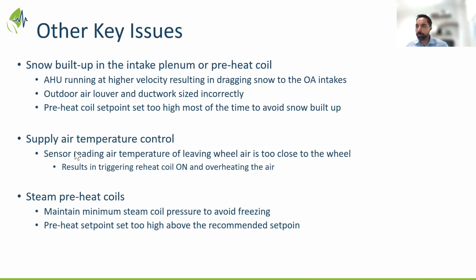The next one is supply air temperature control, which again goes back to where the sensors are located, especially the sensors located close to the wheel's leaving temperature, because these are huge units. The wheels are big, and it takes time for the air to mix. If you have a sensor downstream of the wheel, it could read different temperatures anywhere from 0 to 10 degrees C. That sensor is connected to a PID loop that brings on the heating coil to reach the supply air temperature. The issue we're noticing is that there is sometimes incorrect feedback from these sensors, which triggers the heating coil to come on and overheat the supply air temperature, which then backs off the heating wheel, saying don't do heating, and this whole process eventually results in inefficiency of the heating wheel.